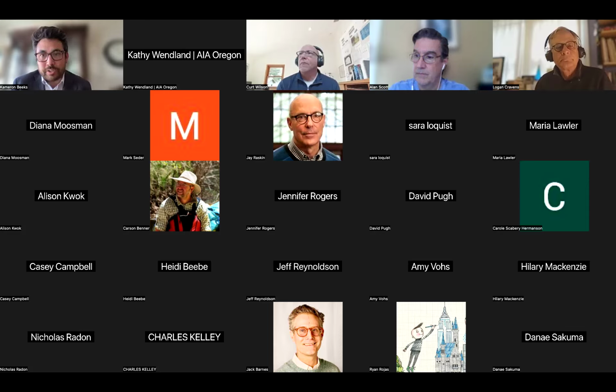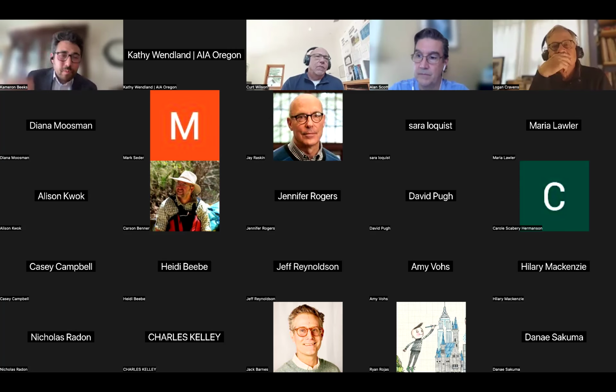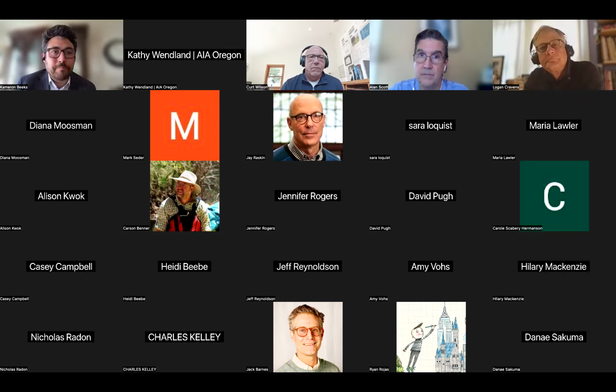So someone asked a question, sorry for talking so long in response to your question, but someone asked about smoke mode. And in your smoke mode, you could simply turn that on or off and it could do a whole suite of modifications to those set points throughout your system. So it should just simply be a toggle on, toggle off of that mode, and it modifies your supply fan, return fan offset, your building pressure, and disables your air side economizer, just to name a couple. So Logan, I'm sorry for the long-winded response.